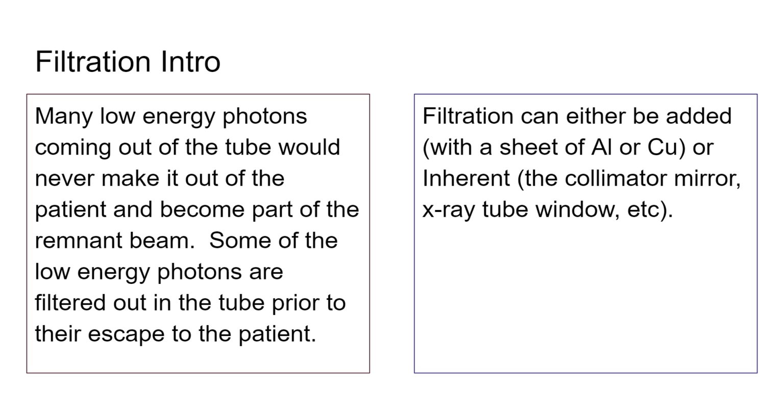So where do you think I am going with this? Title says filtration. What's filtration mean? Don't talk about X-ray. When you filter something, what are you doing? You're getting rid of something, right? Filter your water, go to Newark. Anyway, if we can get rid of some of the X-rays that do not contribute in any diagnostic way to the image, then we can reduce the dose and it's all good. So we have a system called filtration that consists of a way to get rid of some of these really, really long wavelengths. Remember, long goes with weak. The ones that will only contribute to the dose of the patient.